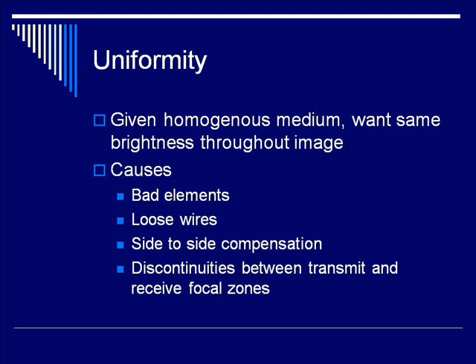If you look and see a non-uniformity, you might see a vertical stripe across the screen where the brightness is lower, or a horizontal band across the screen where the brightness is lower. Those kinds of non-uniformities require you to call the maintenance team for your ultrasound machines. Some causes for non-uniformity include a bad element in the piezoelectric array, a loose wire from one of those elements back to the transducer, problems with side-to-side compensation, and discontinuities between the transmit and receive focal zones.